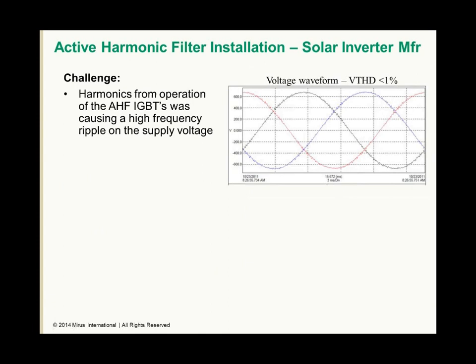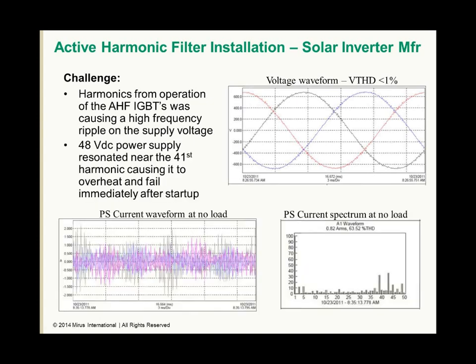When I went to the site and took measurements with a power quality analyzer, I discovered a high frequency ripple on the voltage waveform. Although the overall voltage distortion was extremely low, you can see there's little distortion here, with just a real high frequency ripple. The total harmonic distortion was less than 1%, well within any harmonic requirements. The level of distortion near the 41st, 39th to 43rd, however, was troublesome. You can see this is the current being drawn by the power supply at no load. It's very high frequency. That's shown in the spectrum as being predominantly 39th and 43rd harmonics. The spike in the harmonic spectrum at this level seemed to indicate a resonance condition.